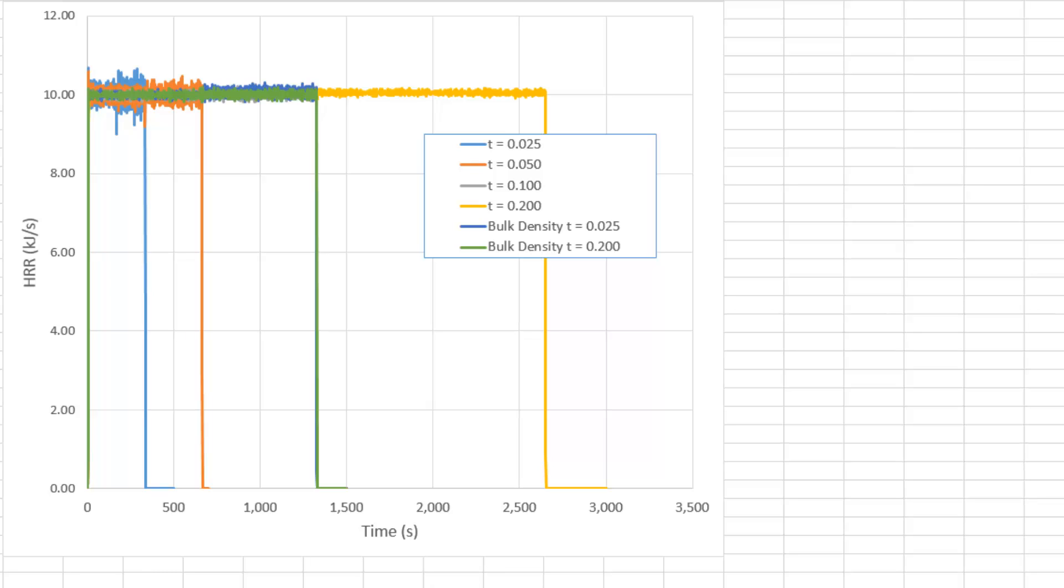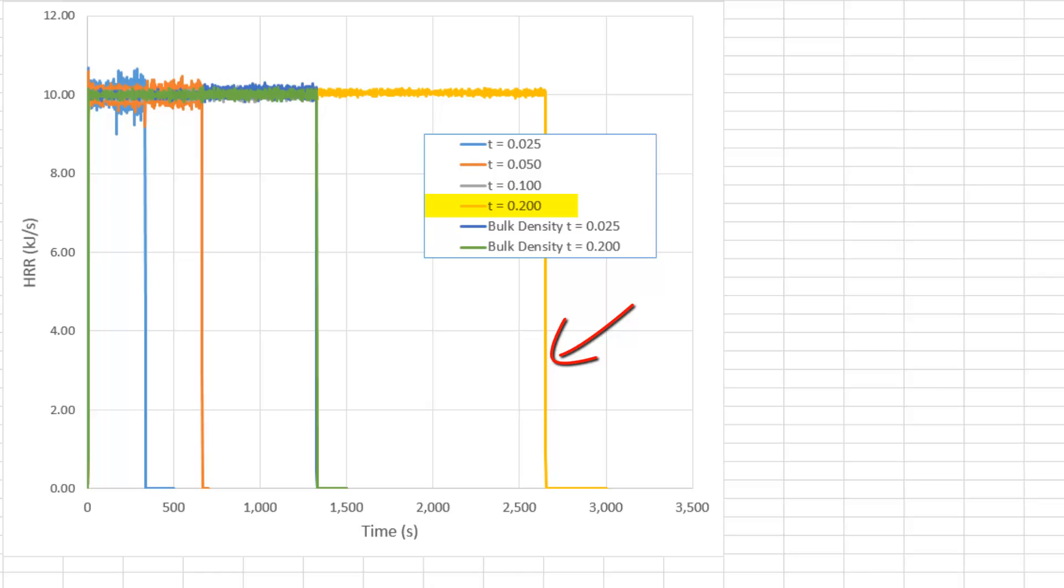When any one surface burns away, the cell block is considered to burn away. This chart shows how using different surface thicknesses changed the total heat release rate. You should always check that the calculated heat release matches the fuel load that you specified.